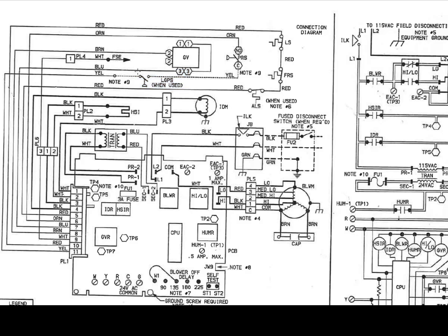So this is normally open. And if you see the symbol, you'll get used to seeing a lot of these symbols, but I know because I've worked on this stuff before that this is a pressure switch. So if you look at this part that I'm highlighting right here, that is a sign for a pressure switch. And this particular switch is a low pressure switch versus what could be considered high pressure switches. And I can tell by the way it's drawn.